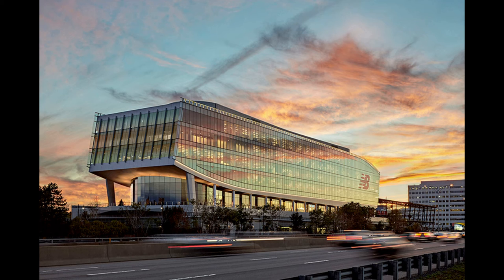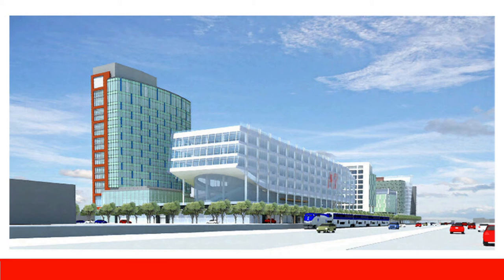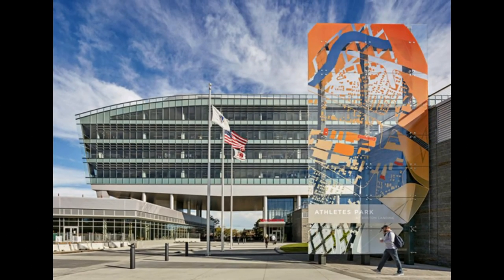able to achieve an optimum indoor environment without considering the building facade and envelope as well. On the south side of the facade, horizontal louvers are installed at ceiling level by each floor's windows, acting as shading devices from direct sunlight and reducing heat convection due to the all glass face. The east and west facades also have large vertical mullion caps, creating a recessed window system to provide sufficient protection from the rising and setting sun.